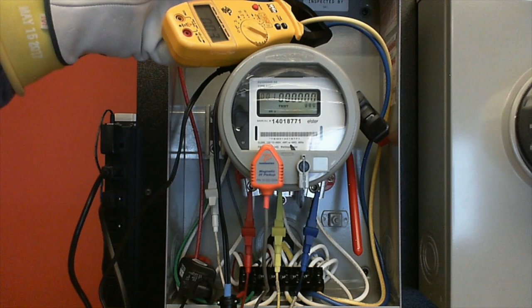So what voltage did you say I'm looking for, Chris? If it's a 4-wire Y, I'm looking for 208, right? Yeah. Okay, so we have a problem here. If we have no voltage and we have no current, let's just verify. If you have this equipment on your truck, guys, use it. We're going to set our voltmeter to current and clamp on that leg. And I have no current going to this meter. Nothing. So that will tell me something's going on.